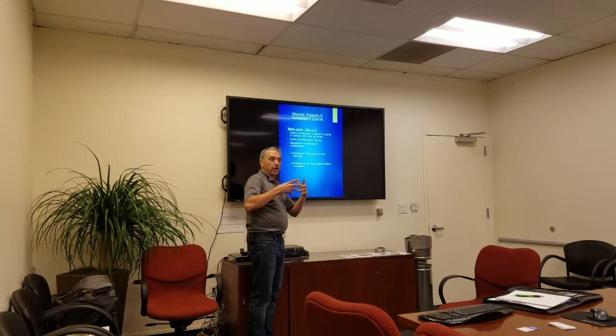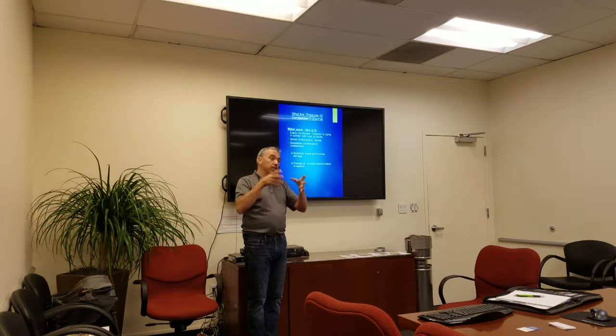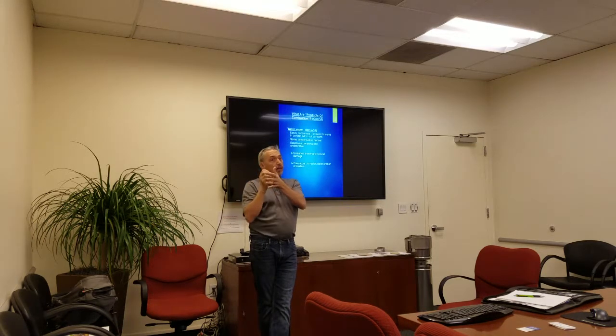If a stack continues to create moisture because the stack stays too cold — maybe it's oversized for our appliance — that appliance doesn't give off enough heat to heat the vent stack and condensation occurs in the stack. We can get dripping, and you'll see a white trail sometimes from type B vent, coming out the seams. That white trail is condensate happening inside the stack.